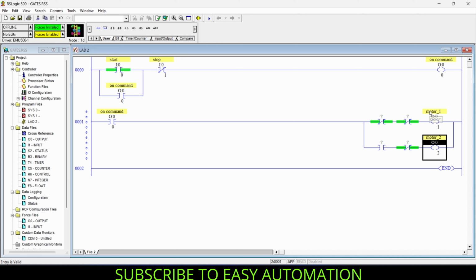And to create one interlock between these two motors, I will just drag the first motor's address to our second motor's NC contact and our second motor's address to our first motor's NC contact, so that if our first motor is on, then our second motor should stop, and if our second motor is operating, then our first motor should stop. It is for the condition where both the motors should not start at a time. So this was for it.